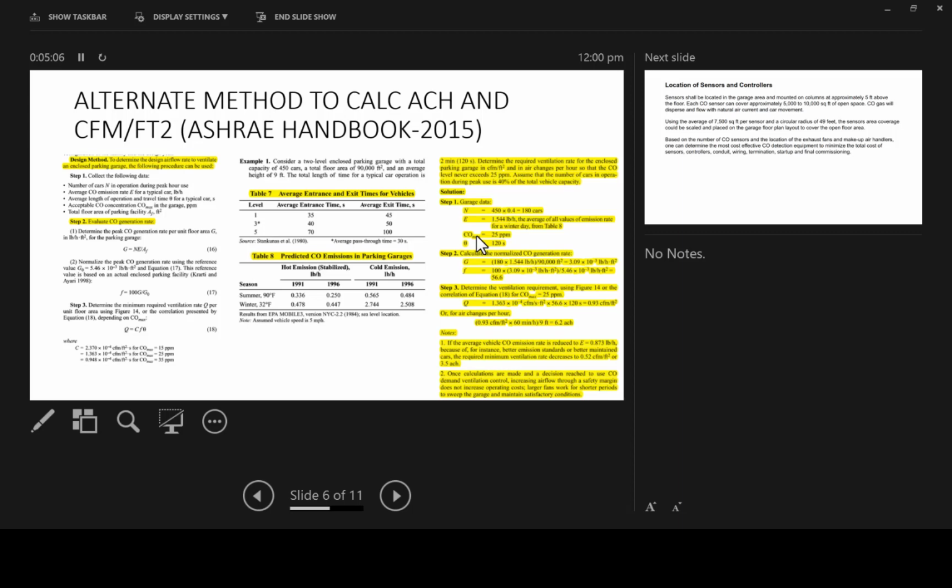You need a VFD drive fan or a three-speed fan to run at different speeds depending on the carbon monoxide level. We consider a maximum of 25 or 35 according to different standards. I will discuss it later. So here we need to maintain 25.